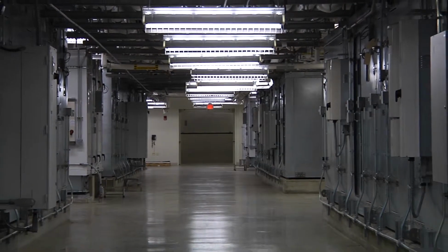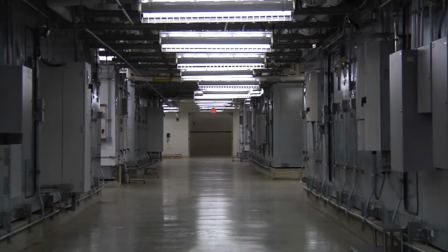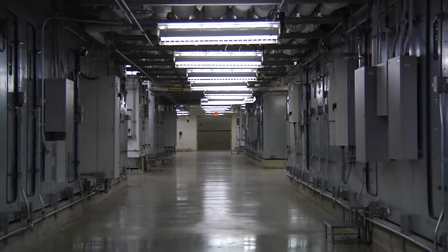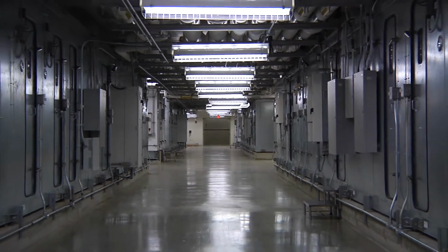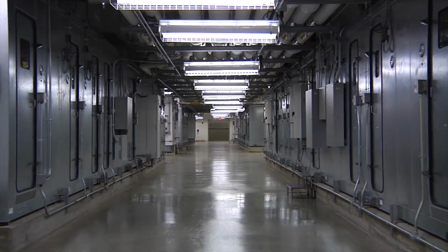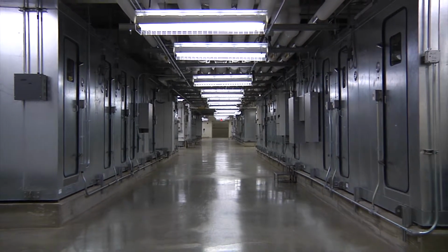Okay, we have air handlers up above the clean room. Very important thing, as I had mentioned, to keep a lot of airflow going through the clean room. So we have makeup air systems where the air comes in from the outside. It goes through several levels of treatment before it becomes clean enough to go into our airstream. It also undergoes temperature and humidity modifications, and then goes into what we call the recirculated air handlers. So it passes through them before it actually gets to the clean room itself.